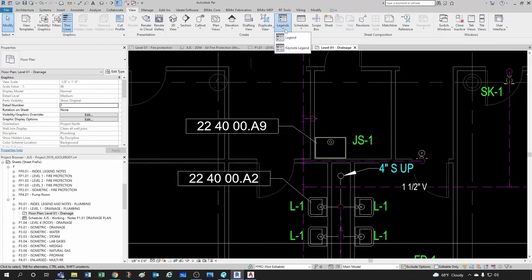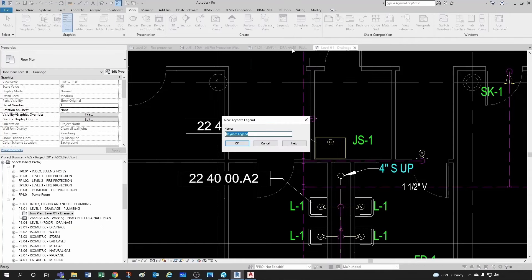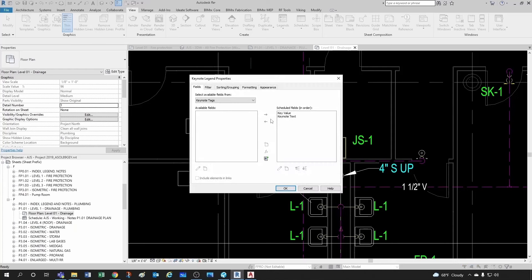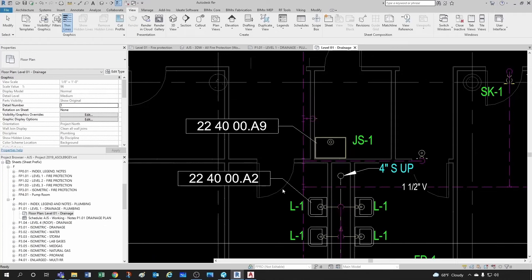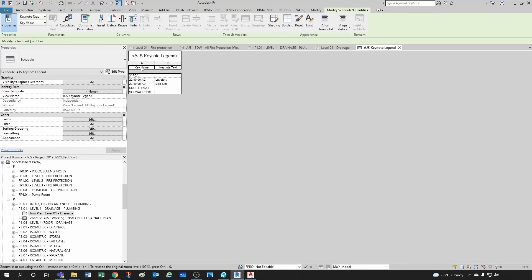For the keynote legend, go to View, then under Legend select Keynote Legend. We can keep this name or call it, say, 'AJS Keynote Legend.' By default we have two fields: a key value and the keynote text — that's fine. Click Accept, and now you can see that the key value refers to your specs section and the keynote text is simply 'lavatory' or 'mop sink,' plus the other key values for fire protection grabbed directly from the model.